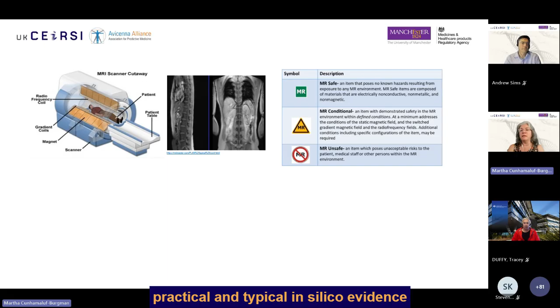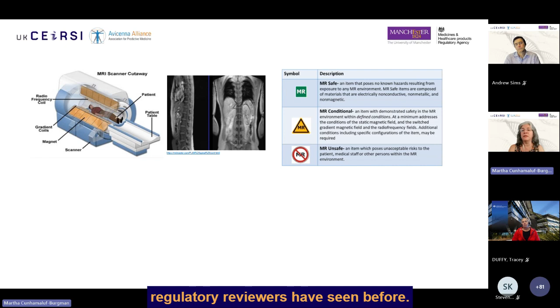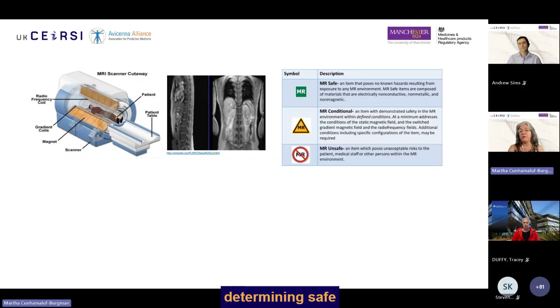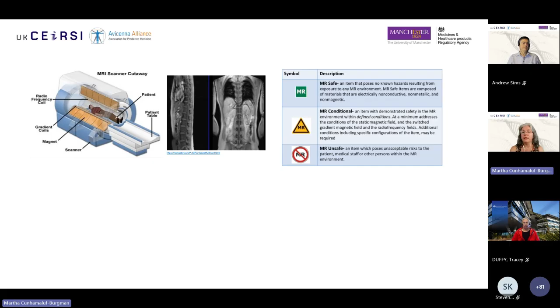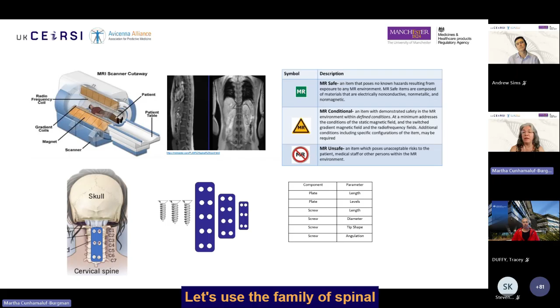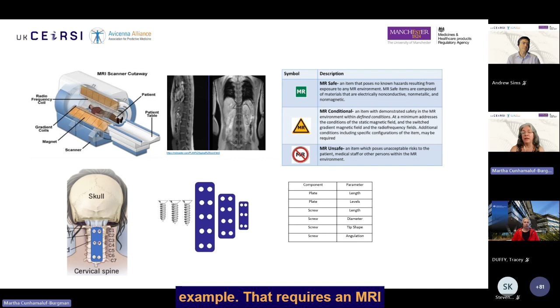So let's go through this using a practical and typical in silico evidence that many regulatory reviewers have seen before, and that is the MRI safety labeling. The labeling allows the clinician to know the safe limits. The most challenging labeling parameter is determining safe scanning parameters that don't create a hazard for patients during radiofrequency heating. Let's use the family of spinal plate screw systems as an example that requires an MRI safety labeling.